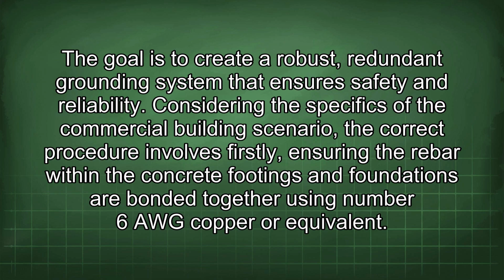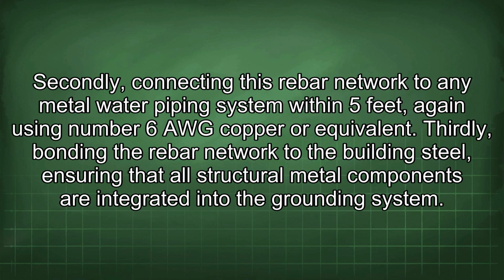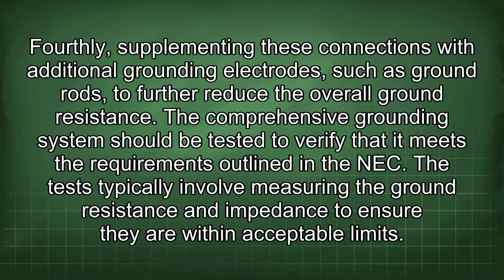Considering the specifics of the commercial building scenario, the correct procedure involves firstly ensuring the rebar within the concrete footings and foundations are bonded together using number 6 AWG copper or equivalent. Secondly, connecting this rebar network to any metal water piping system within 5 feet, again using number 6 AWG copper or equivalent. Thirdly, bonding the rebar network to the building steel, ensuring that all structural metal components are integrated into the grounding system. Fourthly, supplementing these connections with additional grounding electrodes, such as ground rods, to further reduce the overall ground resistance. The comprehensive grounding system should be tested to verify that it meets the requirements outlined in the NEC.